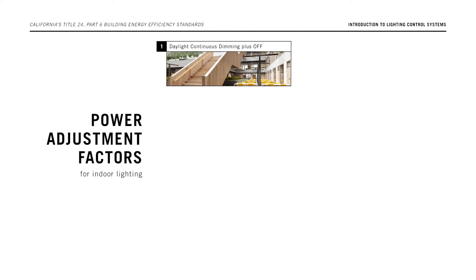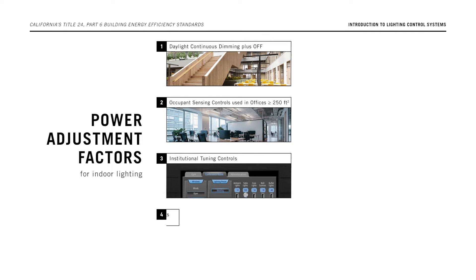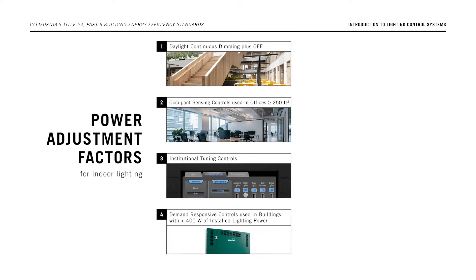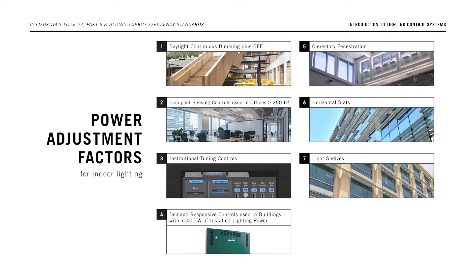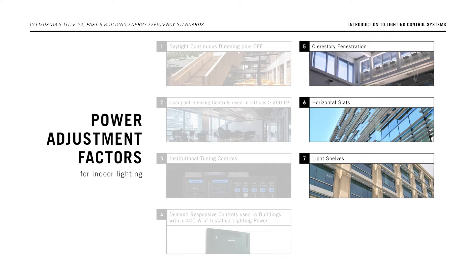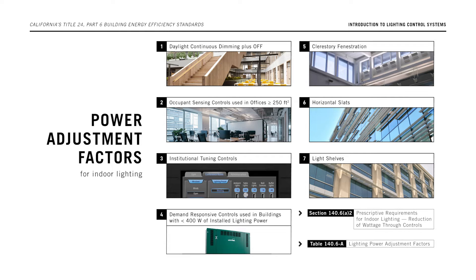They include daylight continuous dimming plus off control, occupant sensing controls used in offices larger than 250 square feet, institutional tuning controls, demand-responsive controls used in buildings with less than 400 watts of installed lighting power, clerestory fenestration, horizontal slats, and light shelves. For the clerestory fenestration, horizontal slats, and light shelf power adjustment factors, the daylighting design must meet the requirements in Section 140.3d. More information on these control strategies can be found in Section 140.6a2 and Table 140.6-A of the energy code.